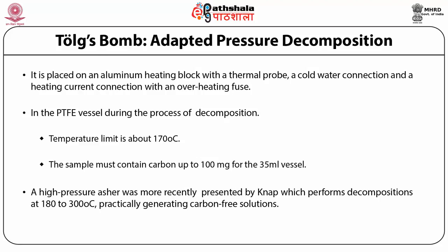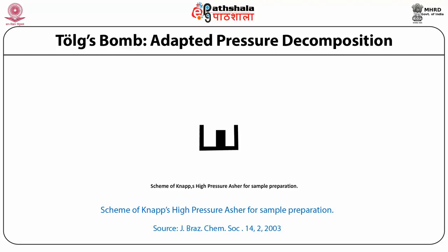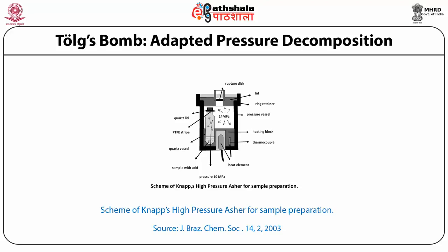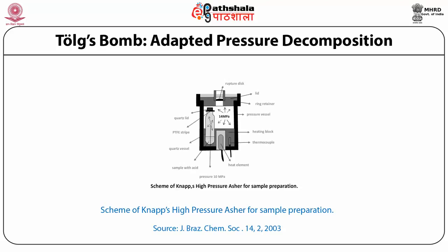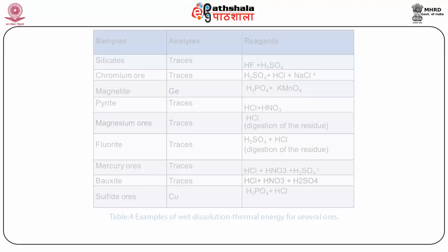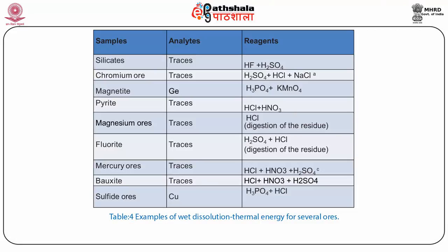A high pressure Asher was more recently presented by Knapp's, which performs decomposition at 180 to 300 degrees centigrade, practically generating a carbon-free solution — developed to overcome the limitations of the Tölg's bomb. The Knapp's high pressure Asher consists of a high pressure vessel which can resist up to 14 MPa of pressure. It has a heating block made of a heating element and thermocouple. Inside the high pressure vessel is a quartz vessel where the sample and acid are placed. The quartz vessel has a quartz lid with a PTFE strip, and also contains a rupture disc — if pressure exceeds the limit, the rupture disc releases.